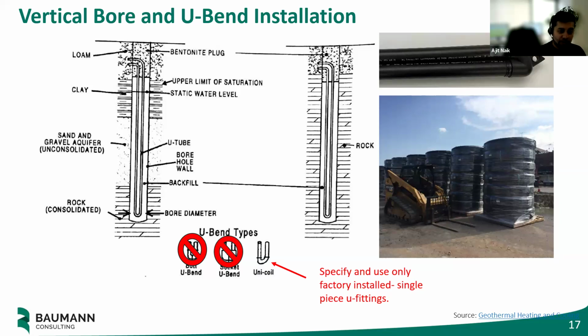A huge piece of pipe, 600 feet into the ground, encased in cement, that's something where you don't want the U-bend failing at the bottom, because it's going to be a pain to get out, or more likely not feasible, and you'll have to abandon that borehole in place. So it's really critical that you design these systems well and install them so you're set up for success. Be mindful of your failure points.